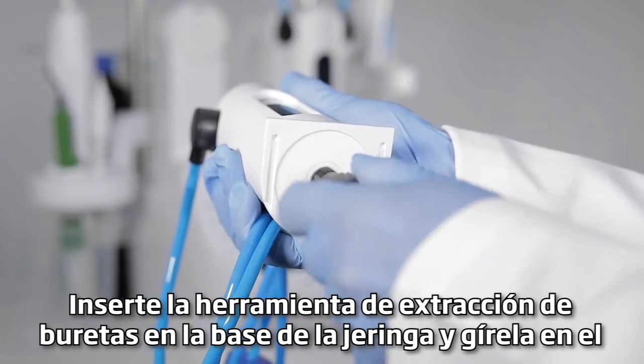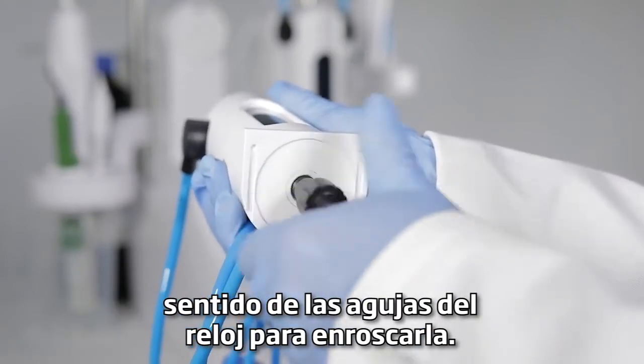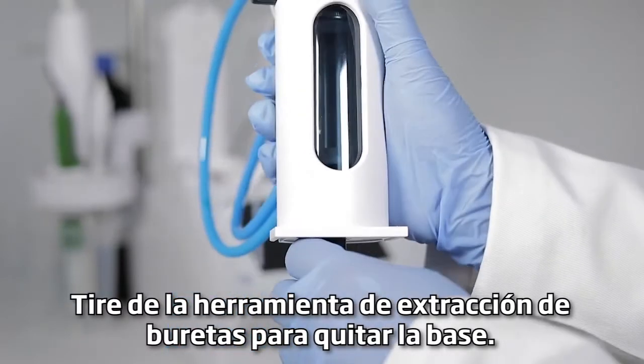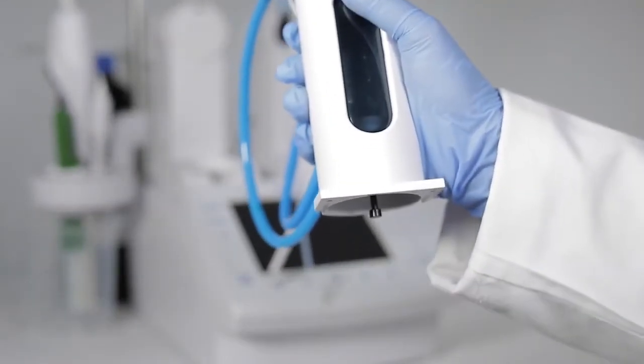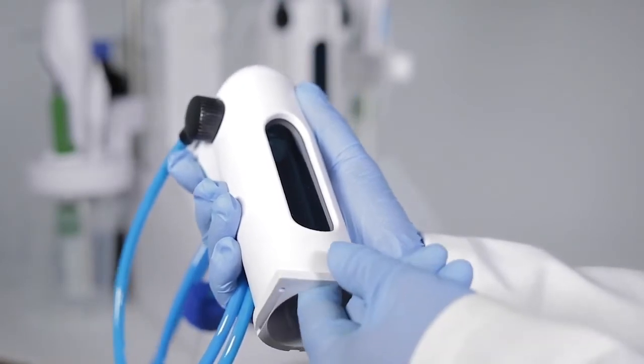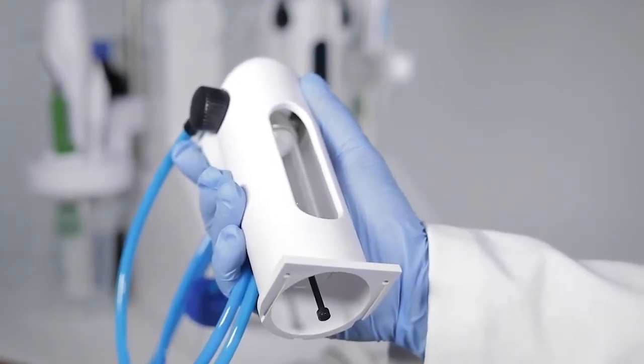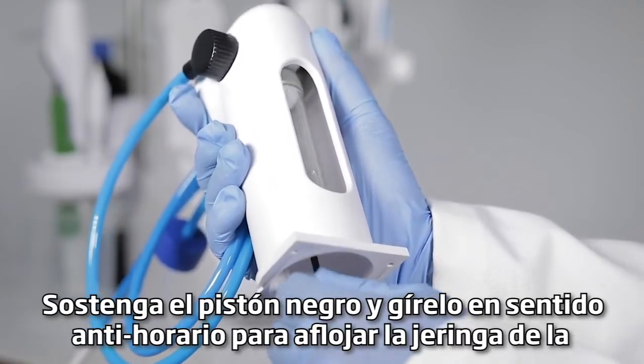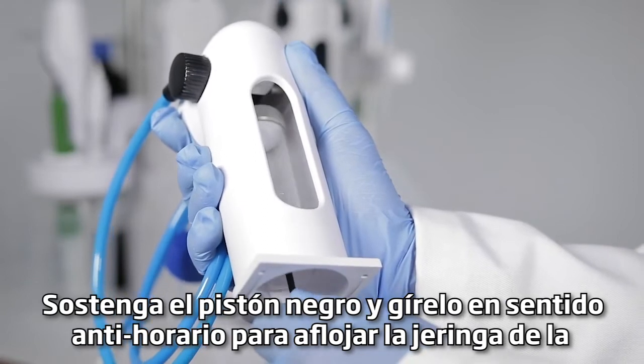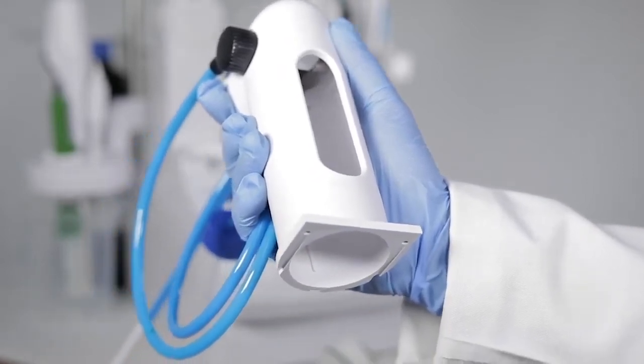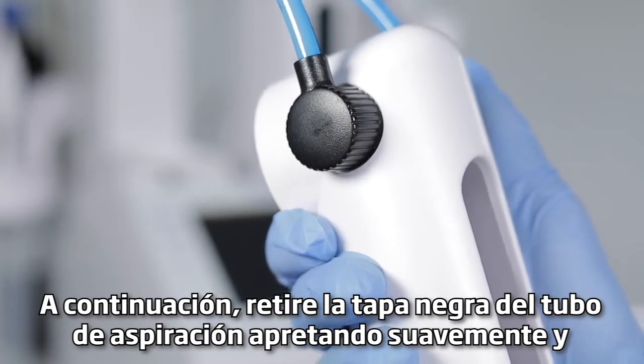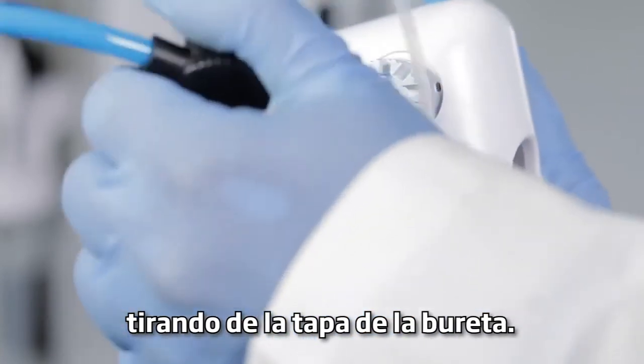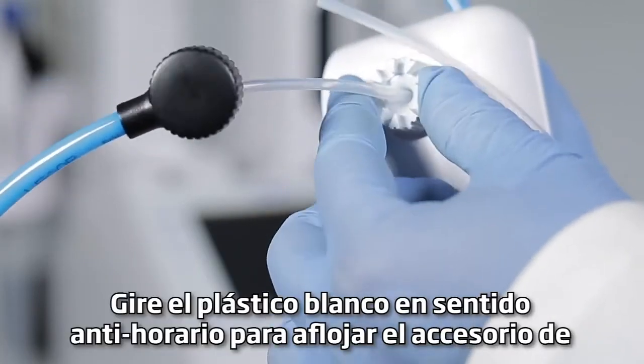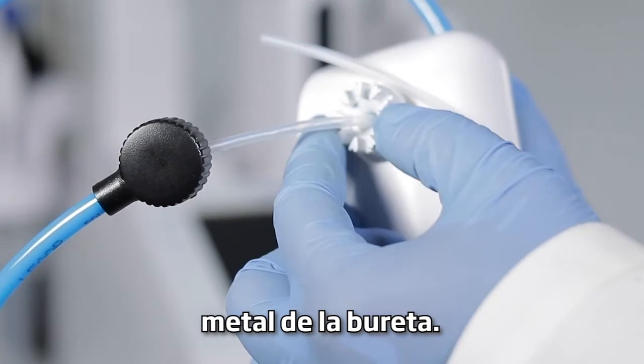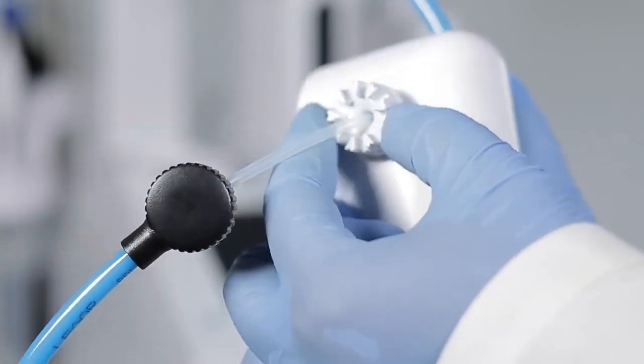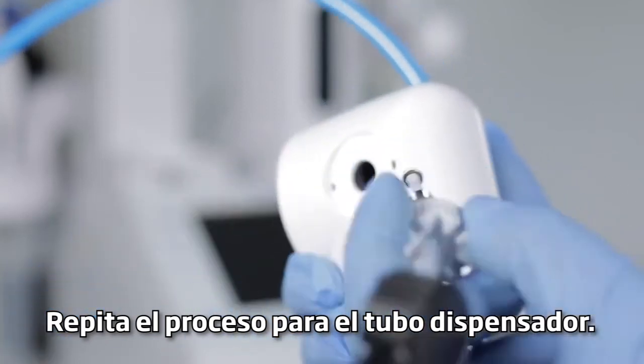Insert the buret removal tool into the base of the syringe and turn it clockwise to screw it in. Pull the buret removal tool away from the buret to remove the base. Hold the black piston and turn it counterclockwise to loosen the syringe from the buret. Next, remove the black cap from the aspiration tube by gently squeezing and pulling the cap away from the buret. Turn the white plastic counterclockwise to loosen the metal fitting from the buret. Repeat the process for the dispensing tube.